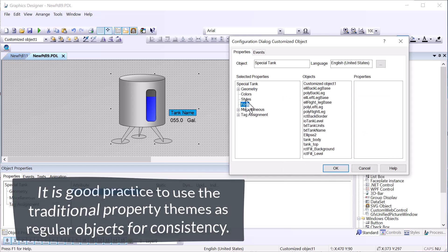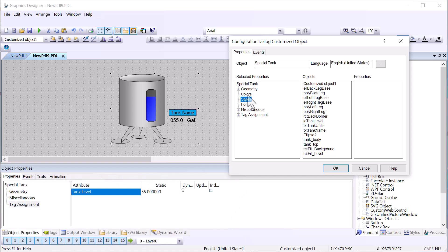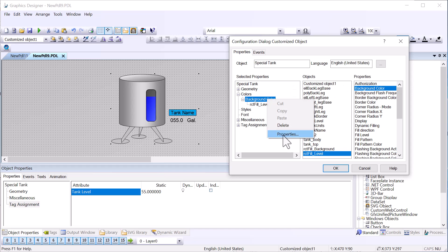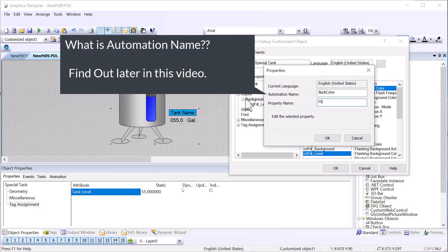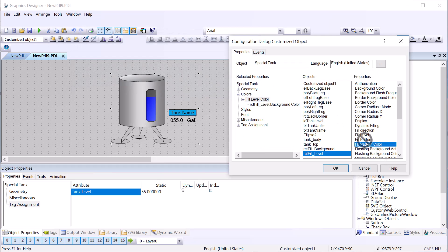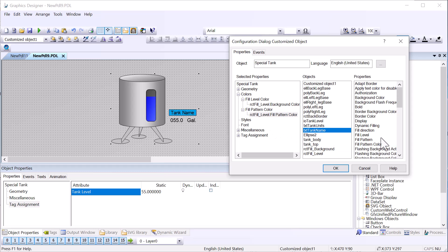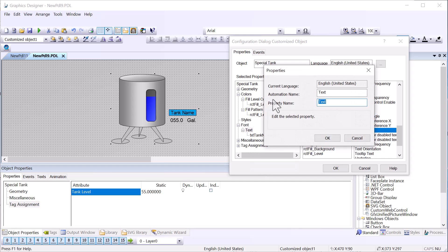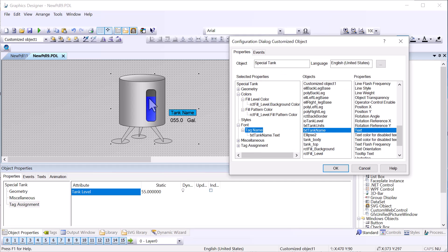All your text-based stuff will go under Font. Your widths and things like that will go under Styles. Your colors will go under Colors. So let's do our fill level color — there's my rectangle fill level. I'll find my background color, put it under Colors, and call this property 'Fill Level Color'. This also has a gradient so I'll make a separate property for Fill Pattern Color under Colors to allow changing the gradient. For the tank name we'll go to our text tank name, drop the Text property under Font, and call it 'Tag Name'.